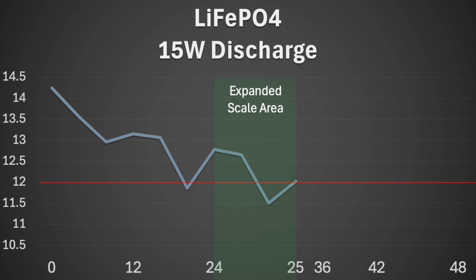At this gentle discharge of just over an amp, the battery isn't particularly stressed. You get a quick initial drop from fully charged voltage, but there's not much actual charge held within that first volt or so. Then the curve is, if you look at the scale on the y-axis, as flat as we know to expect from lithium iron phosphate. All the activity happens within the range of less than a volt, if you discount those dips and recoveries caused by loading and then resting each phase.